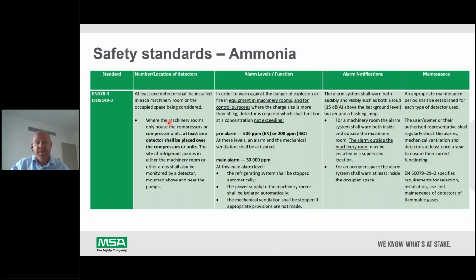There also needs to be 2 alarm levels. So you have a low level alarm at 200 ppm, at which point the mechanical ventilation needs to be activated. Then at very high levels, 30,000 ppm, it initiates a shutdown of the system, because at those levels it starts to get flammability issues. That's usually a large discharge of gas in the plant room. But if you have the early level leak detector at 200 ppm, you're going to know something is happening before the main alarm happens. So early leak detection is very important in these systems.